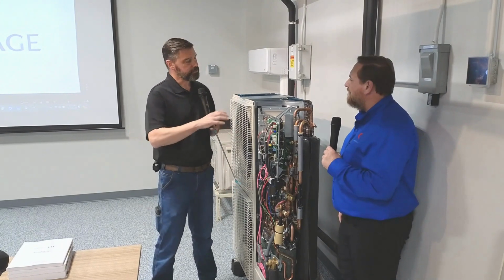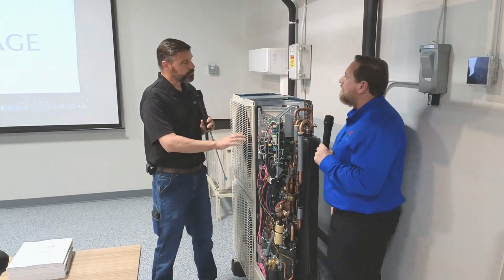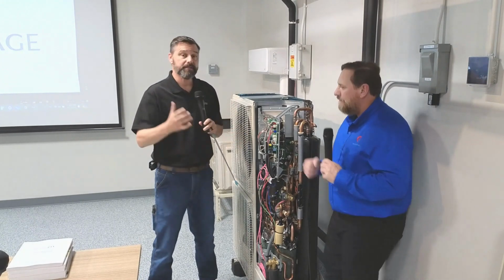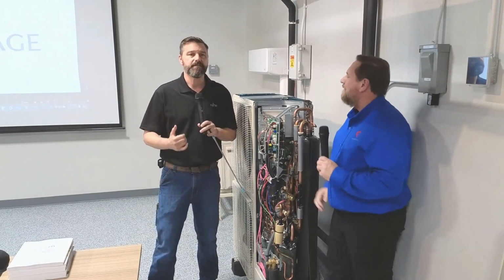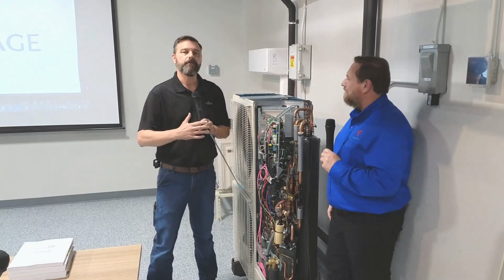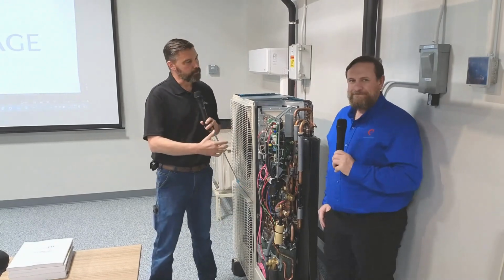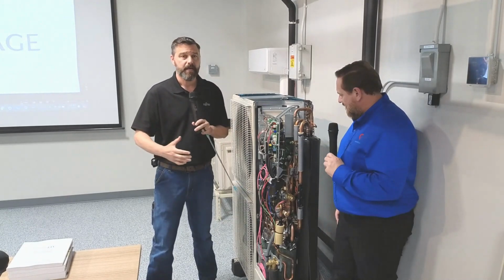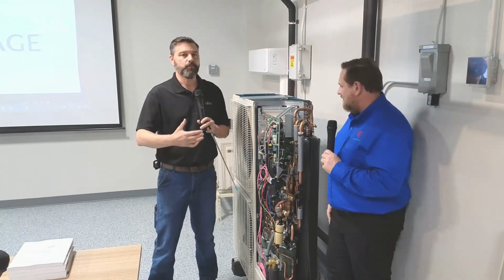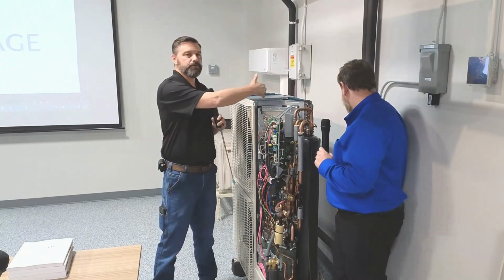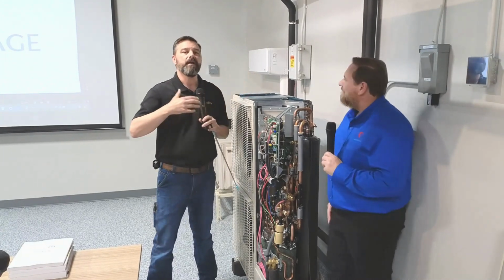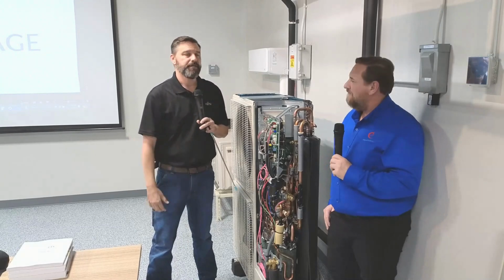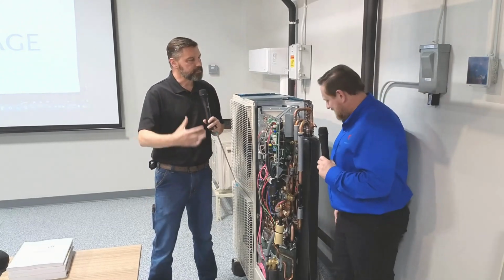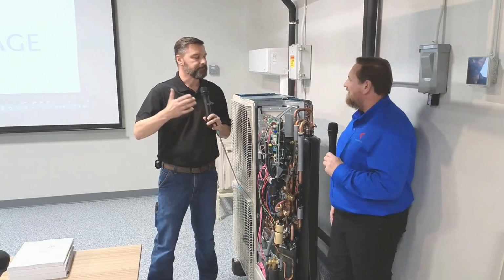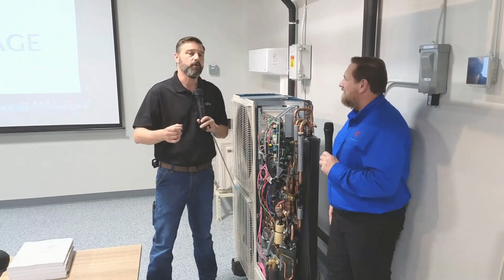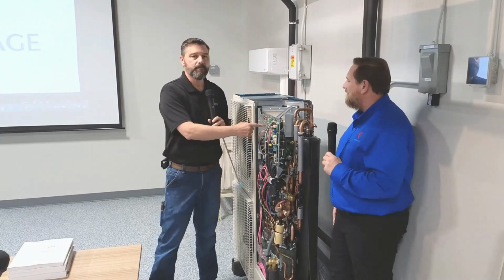Those protections want the system to run, so it will continue to try to operate, but at the same time they'll prevent the system from hurting itself. If we've got a voltage fluctuation in the power coming in, we've got electrical protections. If we've got a transient condition, like a tarp or bag blowing across the back of the coil, we've got temperature and pressure protections in place to help the system run. And eventually, if it just can't run any longer, it will throw an error code on the 7-segment LED.